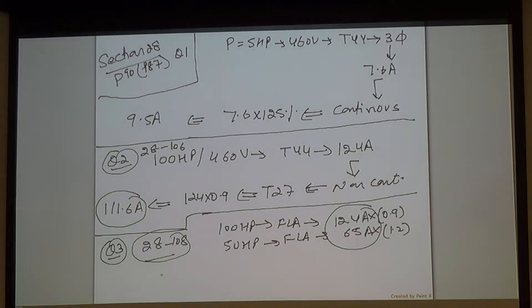So, dear, when you multiply, what's 124 times 0.9? 111.6. And for the second one, which is 65 times 1.2? 78 amps. When you linearly add them, that's when you're going to find the feeder size.